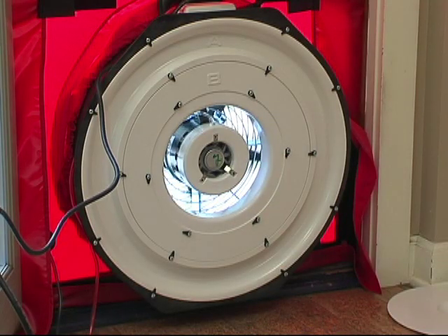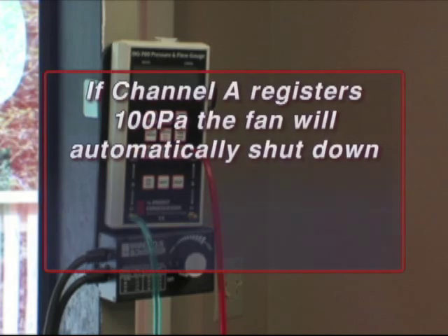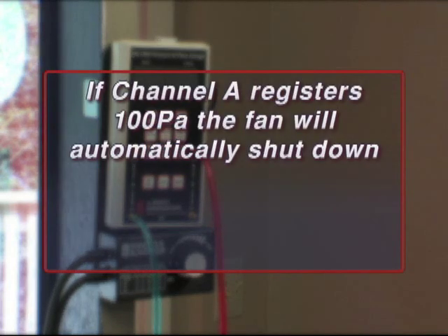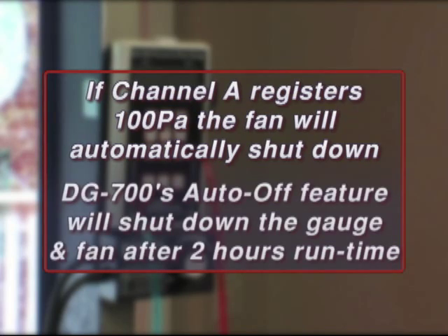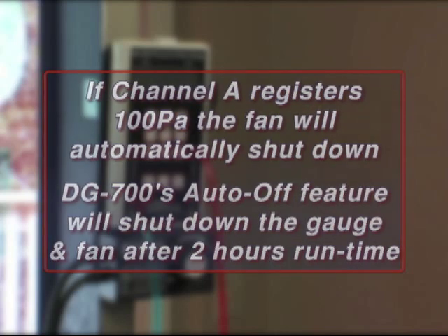The fan will also be stopped while cruising under the following circumstances. If channel A registers a pressure of 100 pascals or more, the fan will automatically be shut down and the gauge will revert back to the cruise setup state. The DG700's AUTO OFF feature will shut down the gauge and turn off the fan after two hours of run time if no buttons are pressed during that time.